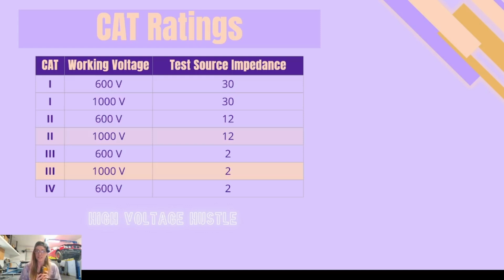The reason this is important is we want the amount of current this component protects us from to be really high. If I divide 600 by 2, I'm protected up to 300 amps of current. A CAT 3 at 1,000 protects me up to 500 amps of inrush short circuit current. So you might ask, why not get a CAT 2 at 1,000? It's a lot cheaper. Well, 1,000 divided by 12 is a lot less current protection than 1,000 divided by 2. So CAT 3 is the way to go.